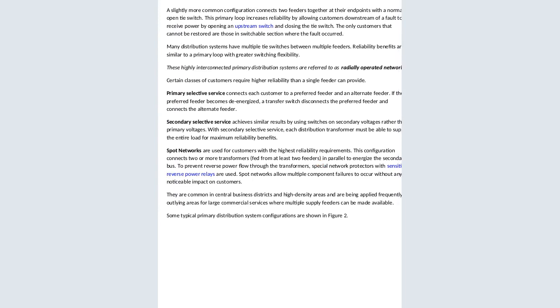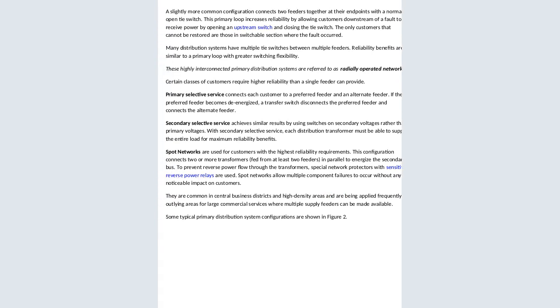Now, primary selective services. Certain classes of consumers require higher reliability than a single feeder can provide. So primary selective services connect each customer to the preferred feeder and an alternate feeder. If the preferred feeder becomes de-energized, the transfer switch disconnects the preferred feeder and connects the alternate feeder. They are called primary customers. These are customers who should not be in a blackout. They're normally the customers who are given priority.